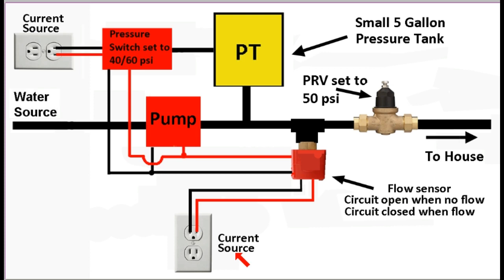which gives very similar functionality to a regular CSV with three advantages. Those advantages being that when the pressure tank is refilled, it refills at the full rate, not at a dribble rate. The second advantage being that when you start up the system, you don't get the initial fluctuation of water pressure. You get a constant water pressure immediately. And the third advantage being, of course, it's much cheaper. So let's see how this system works.